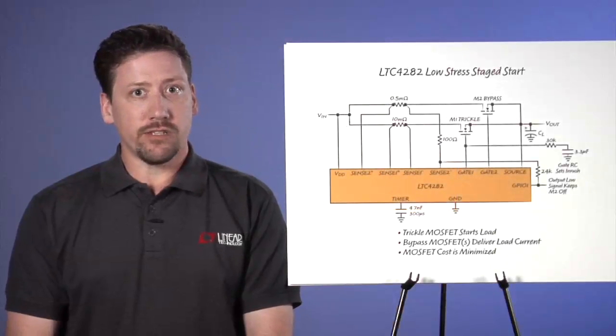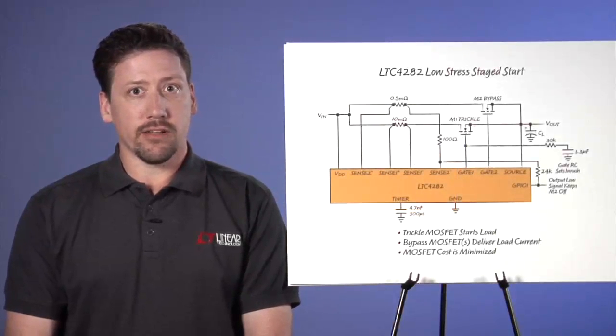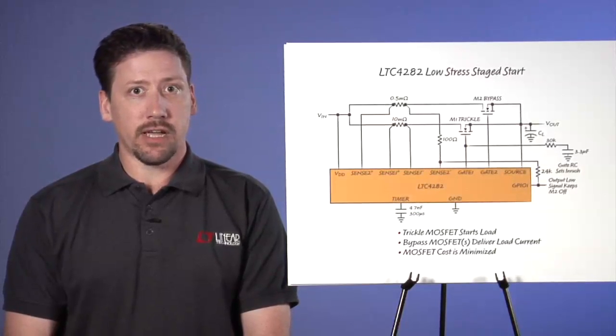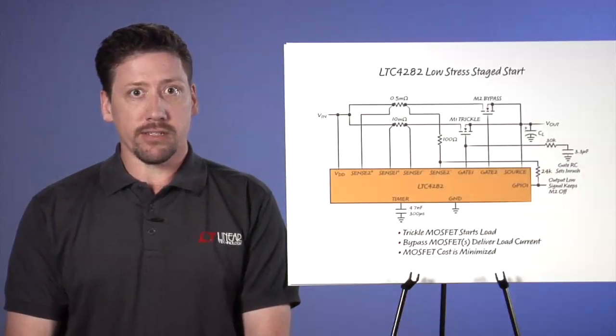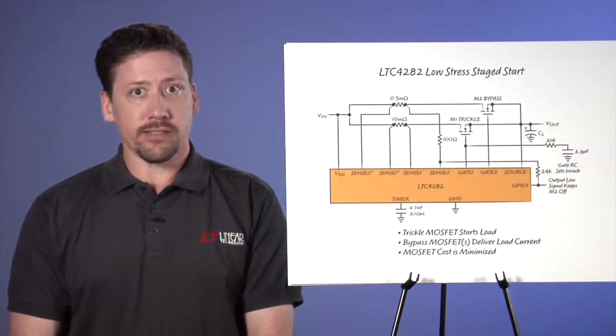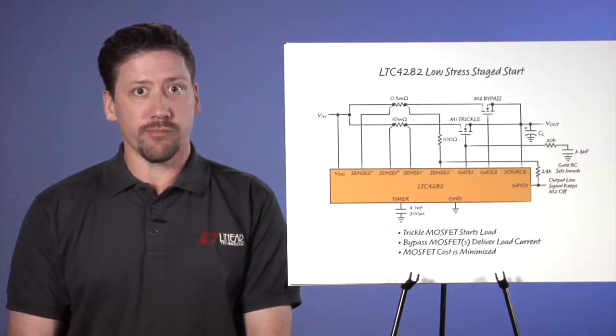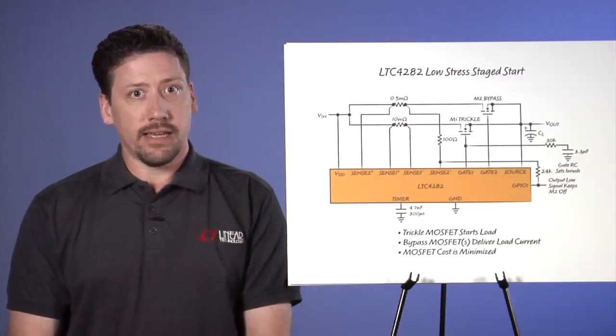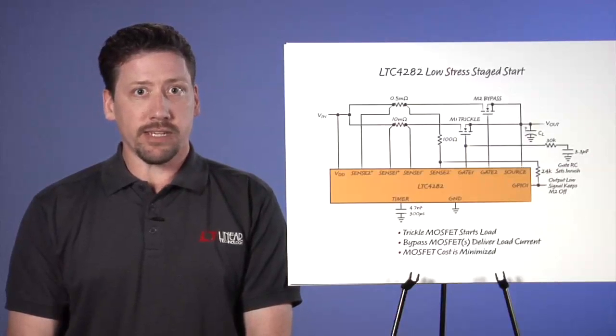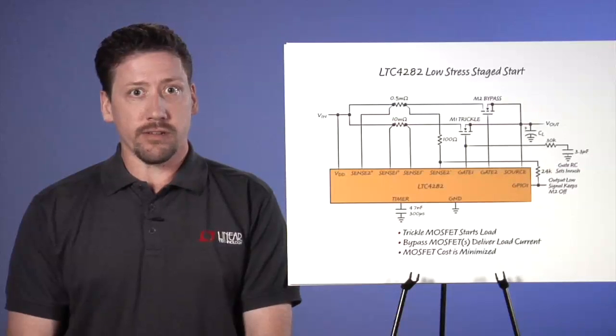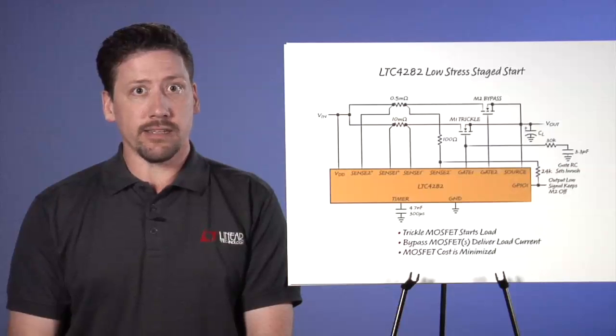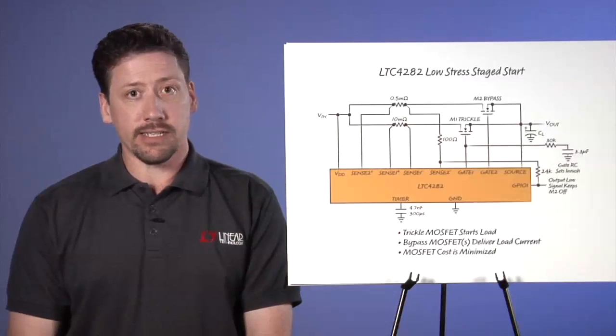The LTC4282 is also capable of two types of staged architectures where the RDS(on) and power dissipation requirements of the hot swap function are separated into two groups of MOSFETs. Each group of MOSFETs is optimized to one purpose rather than trying to find a single MOSFET which has performance on several often conflicting criteria.